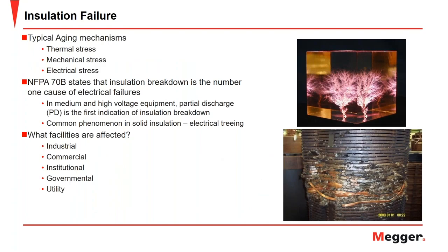So when we talk about insulation, our main concern is insulation failure. There are three typical aging mechanisms when it comes to high voltage insulation, and that is thermal stress, mechanical stress, and electrical stress. Although electrical breakdown is the final failure mode of electrical insulation, electrical stress is not necessarily the dominating aging factor. It's rather believed that the aging mechanism is dominated by thermal degradation, and mechanical stress is caused by vibration and switching pulses. The National Fire Protection Agency states that insulation breakdown is the number one cause for electrical failure.